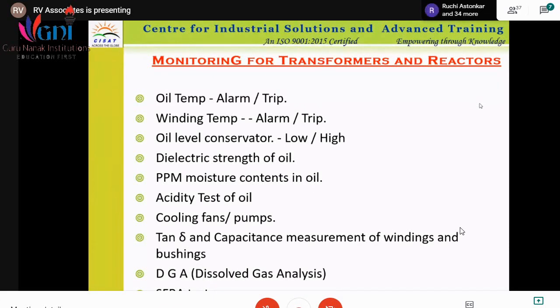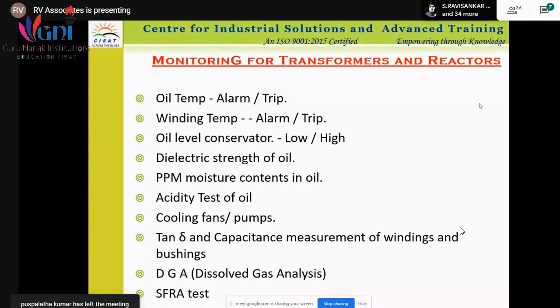So normally at 85 degrees, it will give you the alarm that the temperature is rising. In some industries, they trip at 90 degrees, and in some industries, they trip at 95 degrees. Note that whatever insulation system we are using at present is around 180 degrees. This data is older, from when we were using the class B insulation system, which is about 130 to 155 degrees centigrade. That is the capacity of the insulation system.